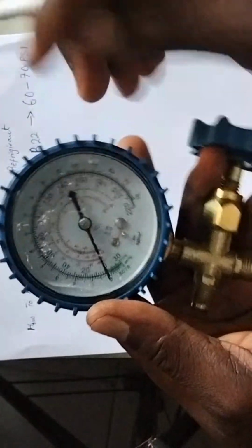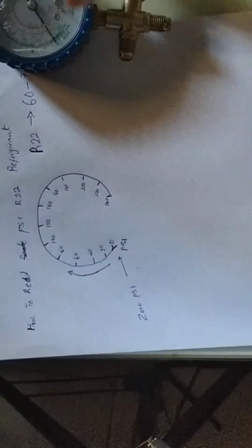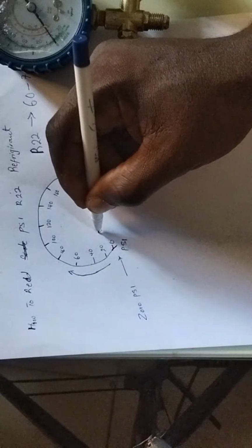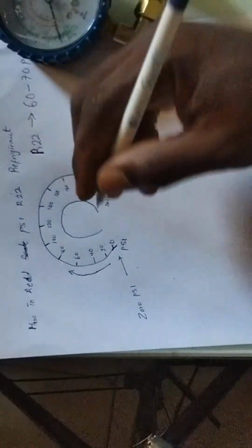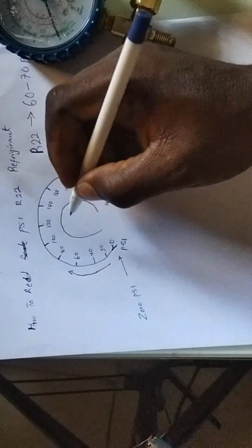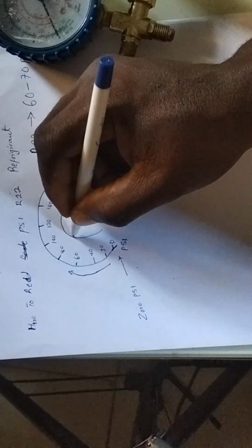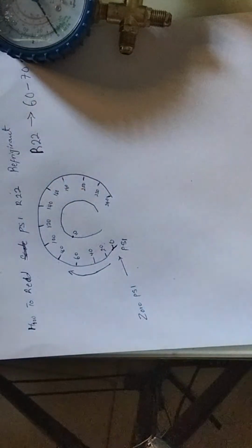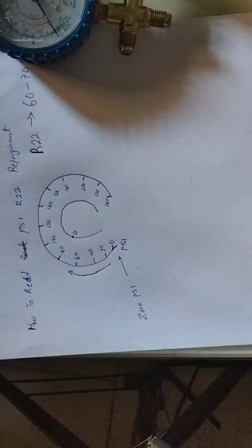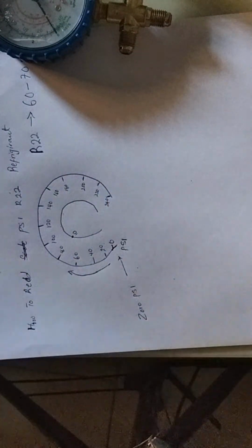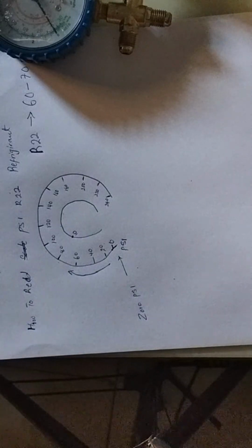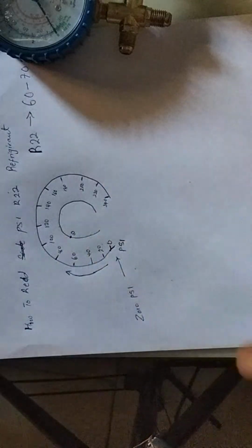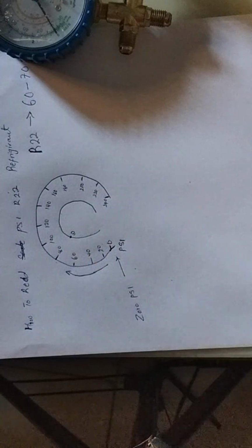Now the bottom part is the inner calibration for us to know the temperature, the boiling point of the refrigerant in the system. You have another inner ring here. This ring entails that R22 refrigerant has a boiling point of about 10 degrees Celsius, which is here. This really means that the heat you always observe behind or in front of your outdoor system is related to the boiling point of that refrigerant. So you see that heat coming out as per 10 degrees Celsius. That is what you observe from R22 refrigerant.